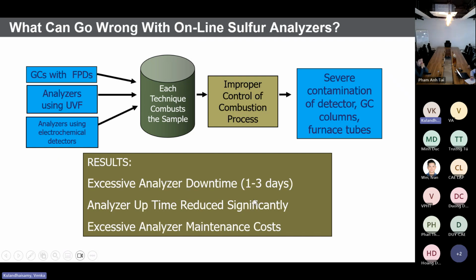Excessive analyzer downtime: if this analyzer is down, it cannot be up within a day. It will take 1 to 3 days. So our SOLA IQ uptime is within 2 to 3 hours; you can bring the analyzer up. So analyzer downtime reduces significantly. Excessive analyzer maintenance costs are also reduced whenever they use the SOLA IQ analyzer.